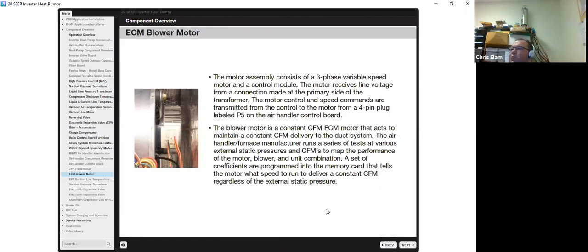The ECM blower motors on these are dedicated ECMs. It consists of a 3-phase variable speed motor and a control module. The motor receives line voltage from a connection made at the primary side of the transformer. The motor control and speed commands are transmitted to the motor from a 4-pin plug labeled P5 on the air handler board. The blower motor is a constant CFM ECM motor and acts to maintain a constant CFM delivery to the system.